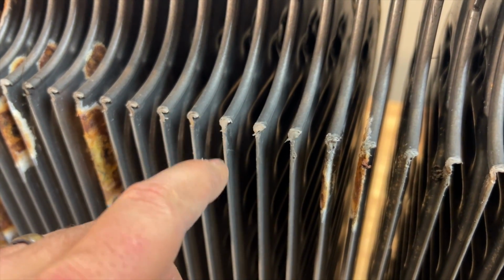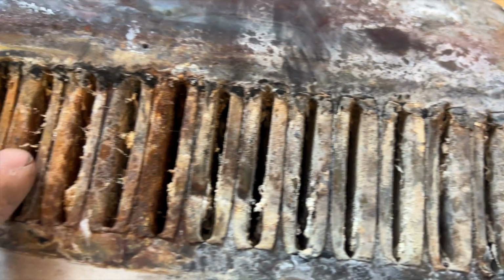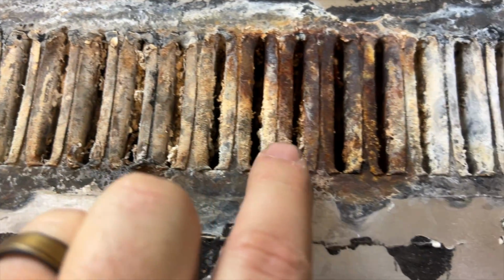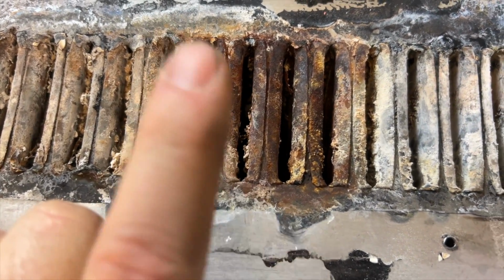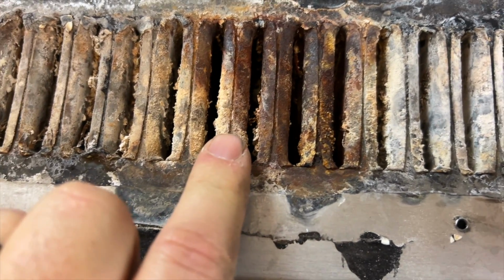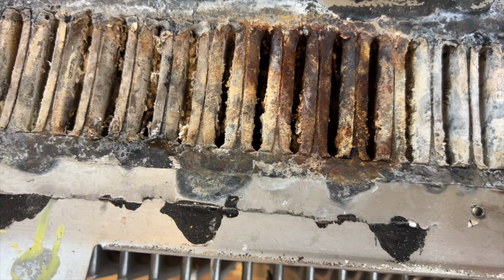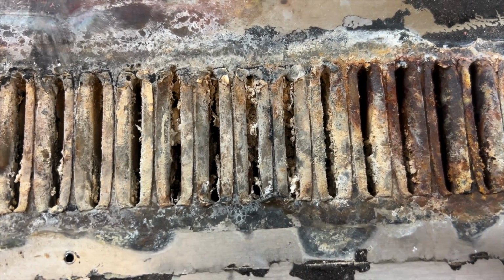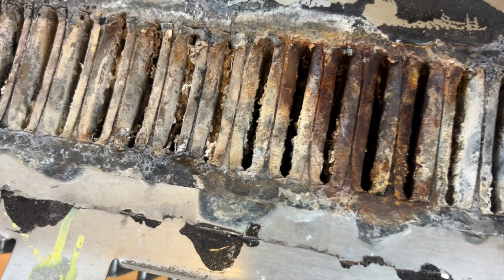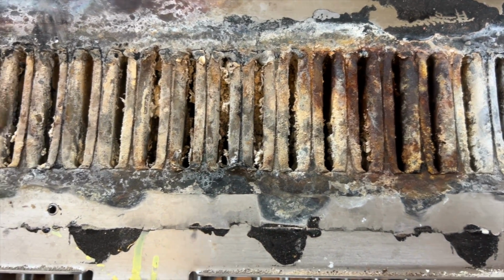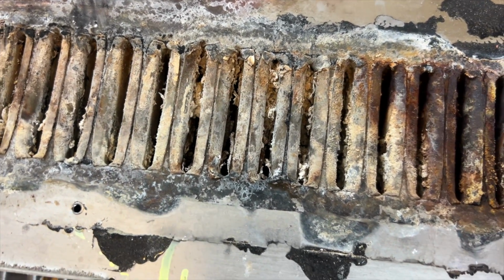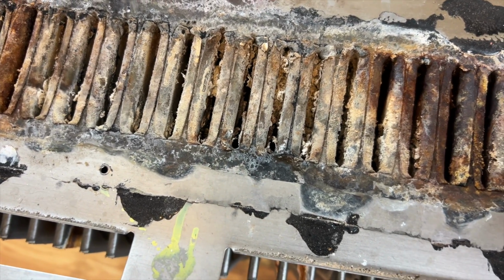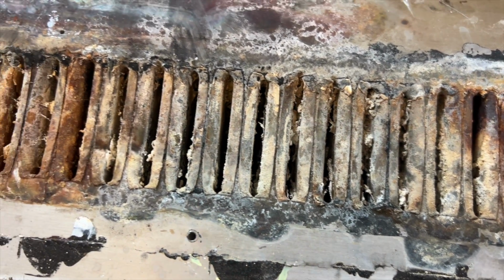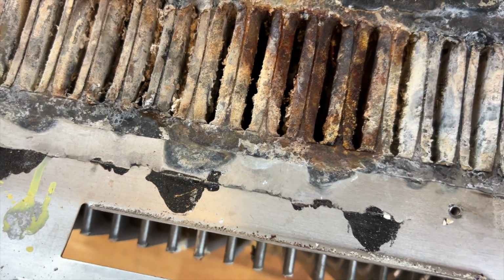Now another thing too is where the transfer box goes, that's where the hot air from the primary will enter the secondary. So here it is. You can see it is completely nasty. And this is a fact that this unit was not properly commissioned. So when you install a new unit, you can do a startup, which is one thing, and then you also do a commissioning, which is another thing. They're not the same. Startup, you turn it on, everything comes on, it works, you're good to go. Commissioning, you start it up, you actually check the gas pressure, you do combustion analysis, you check your refrigerant, all that stuff. Make sure everything's good, then you call it commissioned.